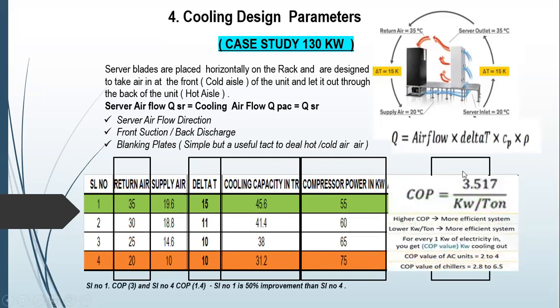So thereby, what happens when you calculate the COP? What is COP? Coefficient of performance. 3.516 divided by the kW by ton. If you see the serial number 1 would give you a COP of 3 vis-a-vis the serial number 4, which would give you just 1.4. That means to say an improvement of 50% over the COP.